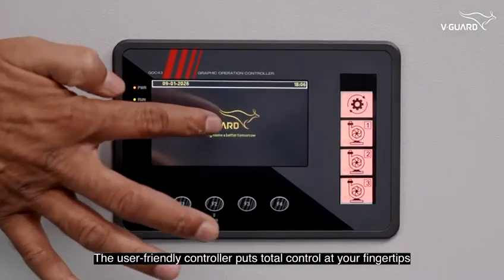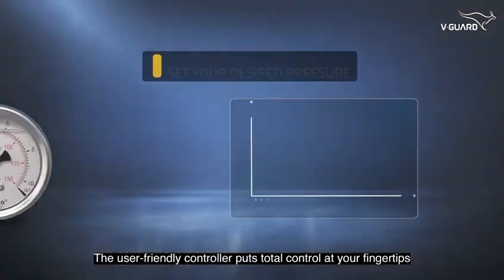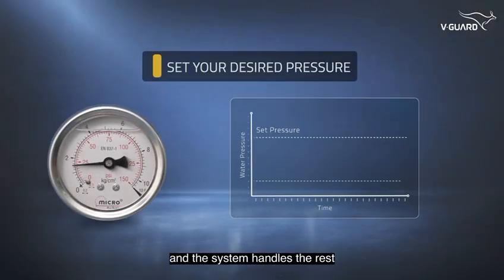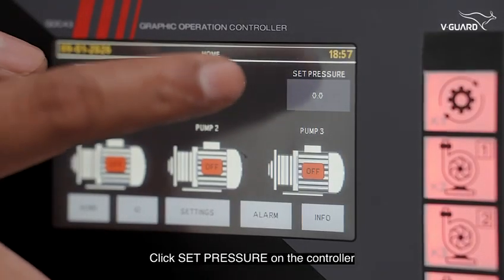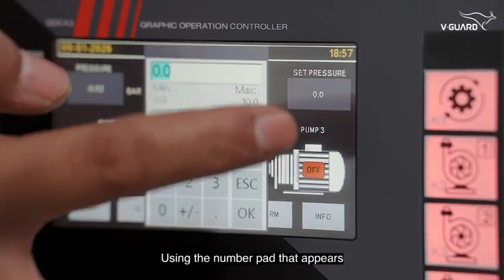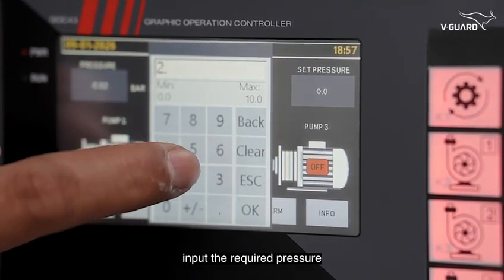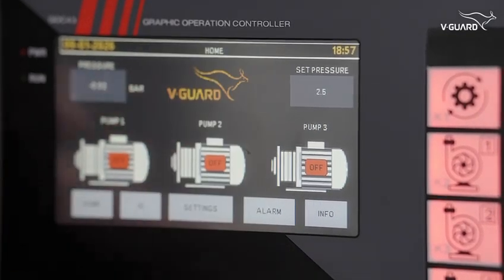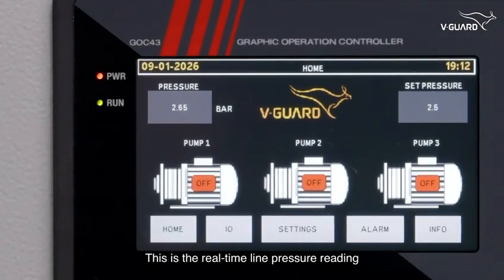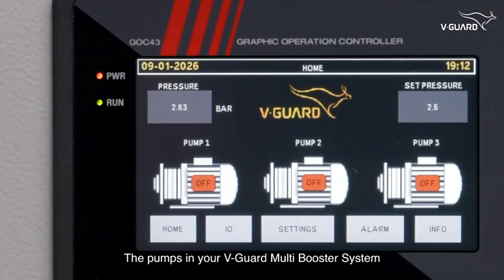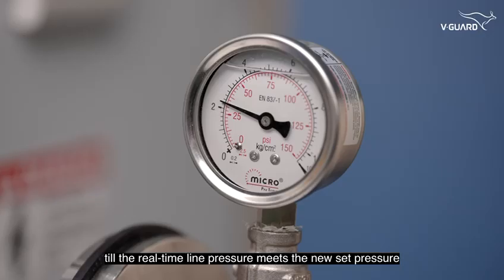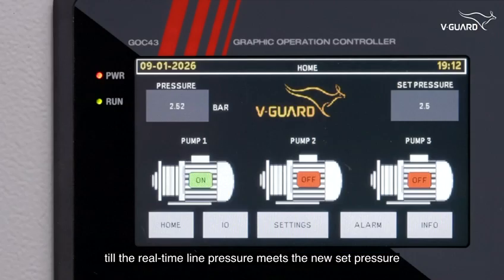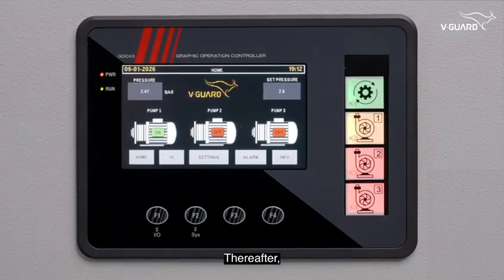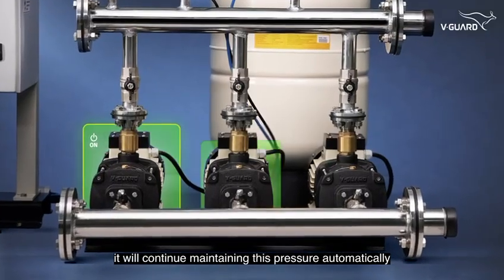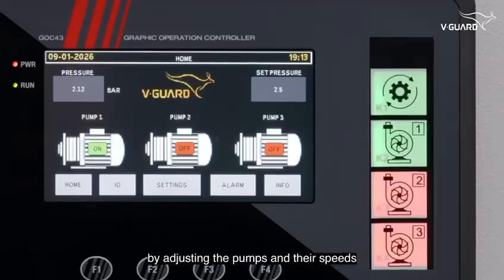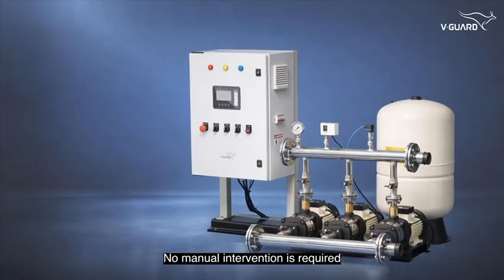The user-friendly controller puts total control at your fingertips. Set your desired pressure, and the system handles the rest. Click Set Pressure on the controller. Using the number pad that appears, input the required pressure, click OK. This is the real-time line pressure reading. The pumps in your V-Guard multi-booster system will continue working till the real-time line pressure meets the new set pressure. Thereafter, it will continue maintaining this pressure automatically by adjusting the pumps and their speeds. No manual intervention is required.